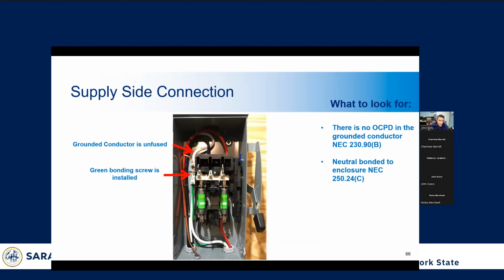And so in light of the fact that supply side conductors are similar to a second set of service entrance conductors, and that they are kind of unprotected from utility side current potentials, the disconnect that serves a supply side connection must be bonded similarly to a service panel, where the neutral and the ground are bonded to the enclosure. So this is different from the disconnect we saw earlier. You can see here the neutral and the ground are bonded together with this green bonding screw, so that's done correctly. And so that also bonds the enclosure and grounds it so that it's safe to touch, basically.